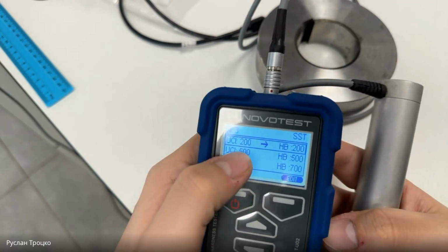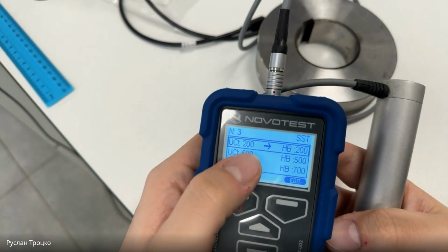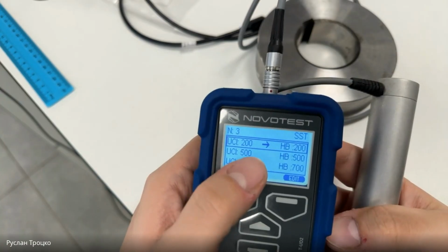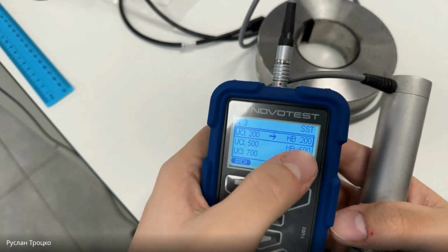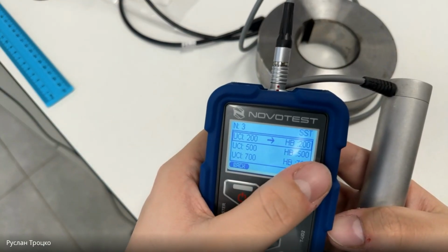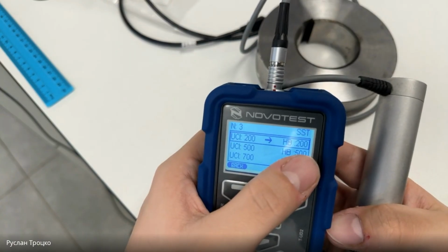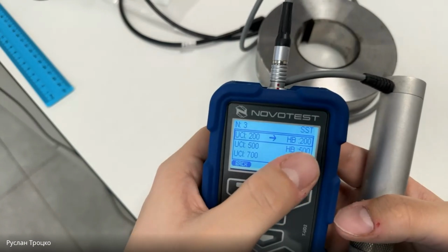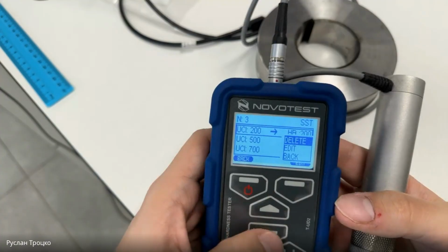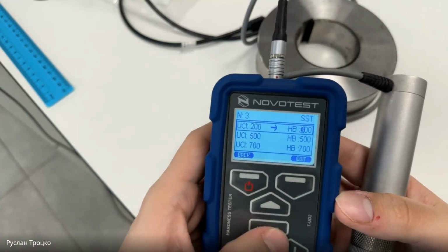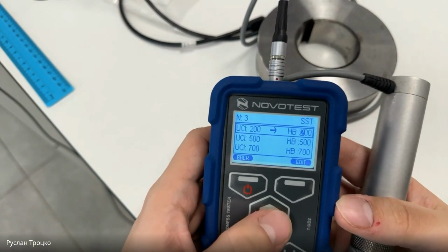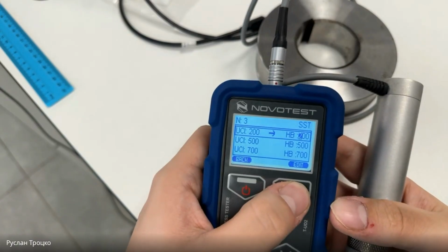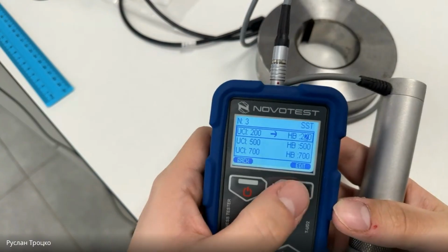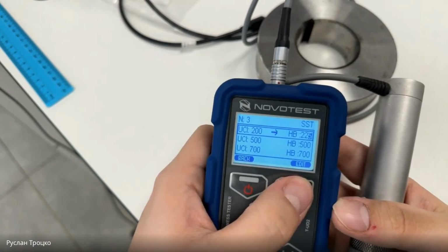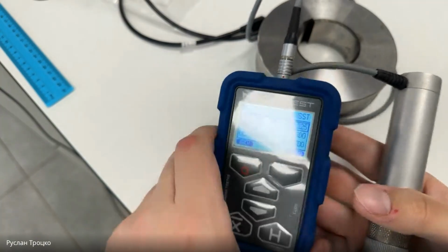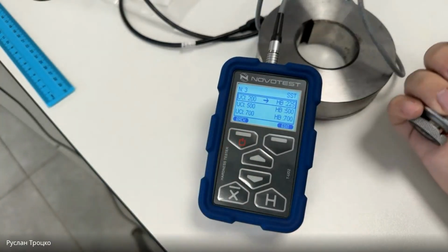Okay, this is the UCI code. This is not a hardness, but this one here is the nominal value, the nominal of your block. If you have a 200 HB block, edit. You can change it. For example, I want to have 225. Okay, now it's 225. And I need to do 5 measurements on the first one.